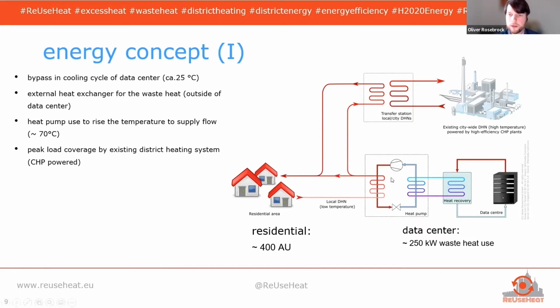We do not have enough heat recovery or waste heat available, given this huge shift between summer demand and winter demand. So we use the existing district heating network as the peak load coverage for this subgrid. A new subgrid was installed, where the heat is generated first of all by the heat pump that uses the waste heat from the data center. And for the peak load coverage, we also have the connection to the existing district heating network with a high temperature.